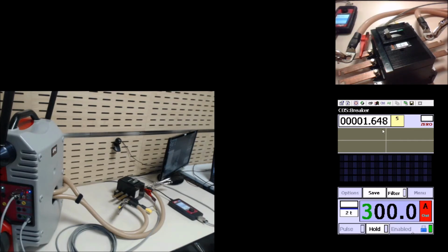So you see the chronometer is now running here, okay? From the very beginning of the test, it starts running. It will be slightly long because at 300 ampere, we are in the very beginning of the curve. So it will take quite a few number of seconds before tripping.